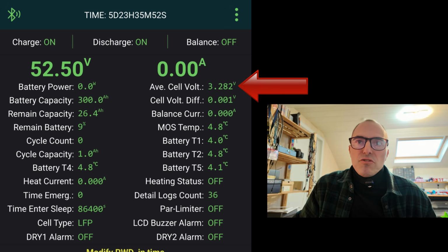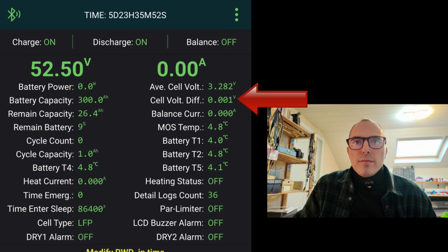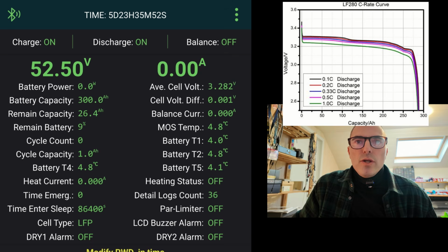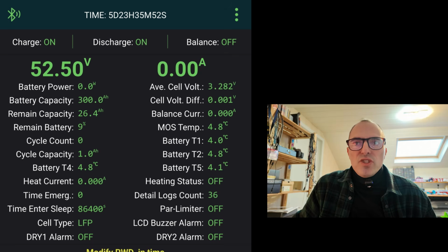Average cell voltage speaks for itself. Cell voltage difference is the voltage difference between the lowest and the highest cell. When in the flat zone, it should never be more than 20 millivolt or 0.02 volt. Typically it's 0.002345 volt, so it's a very small number. The balance current is the current flowing from the highest to the lowest cell when balancing is active. MOSTemp is the real-time temperature of the MOSFETs inside the BMS.